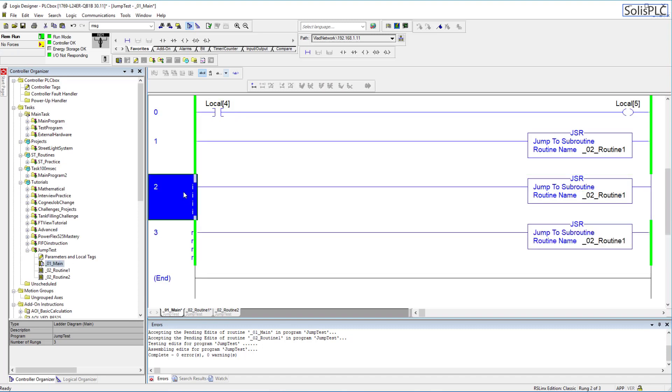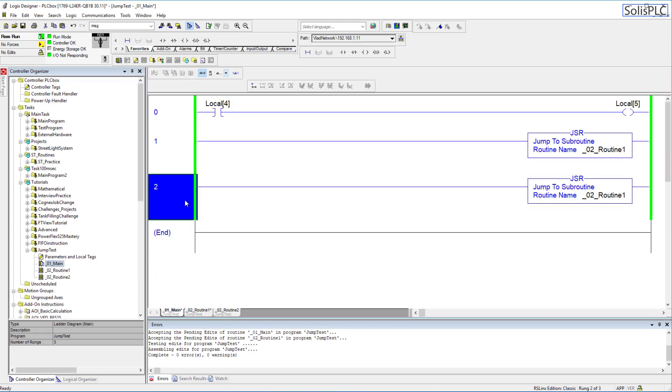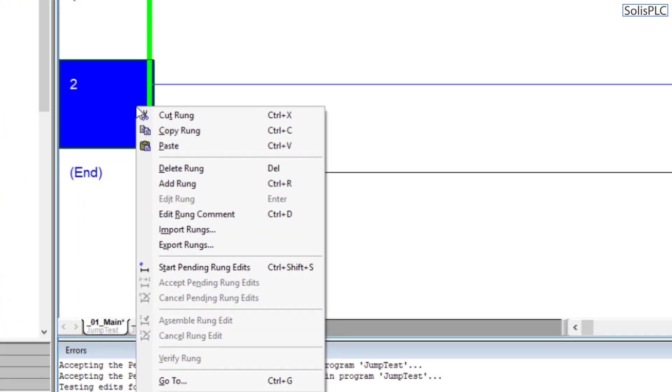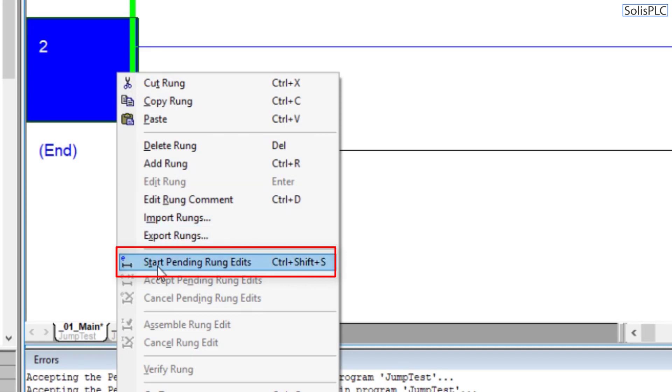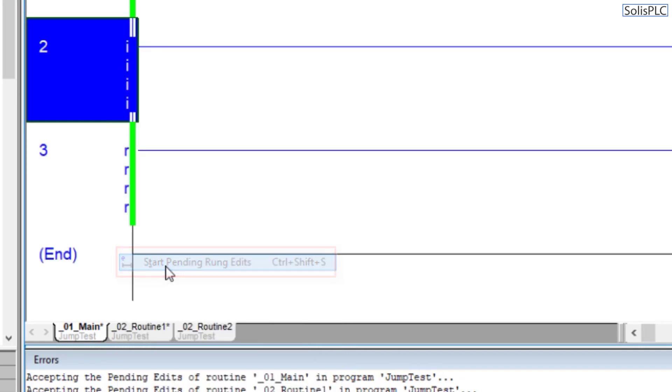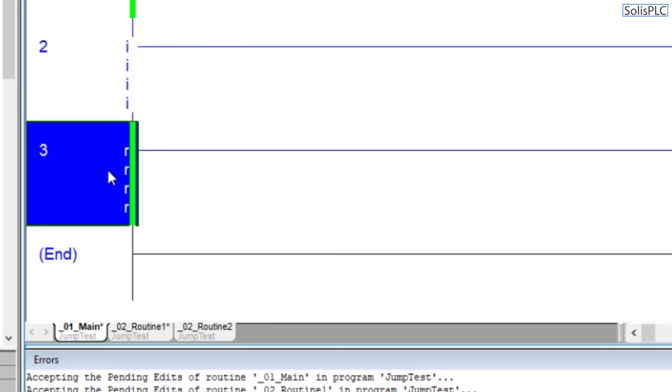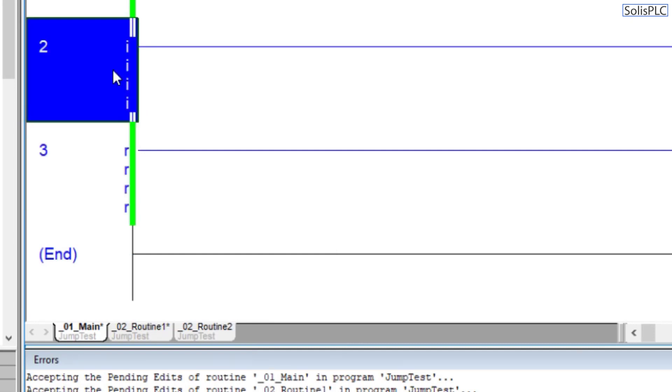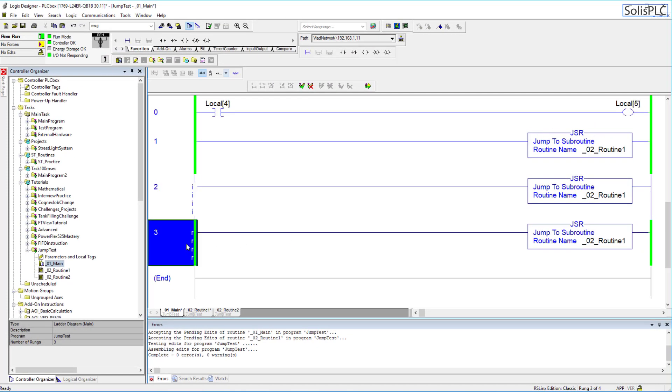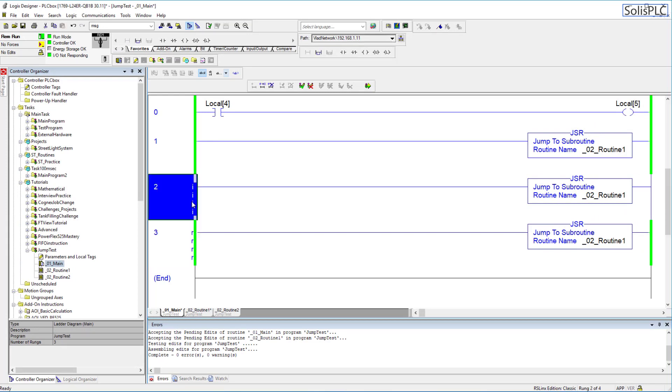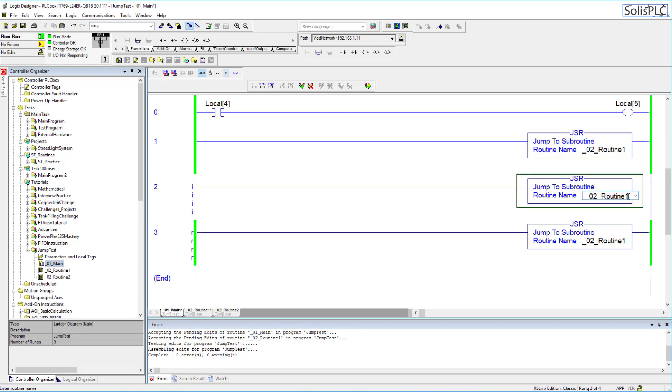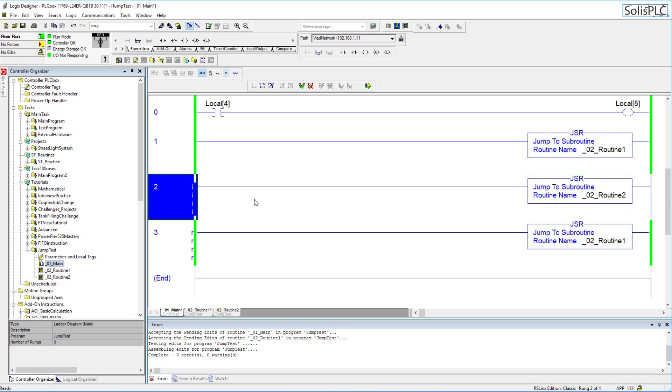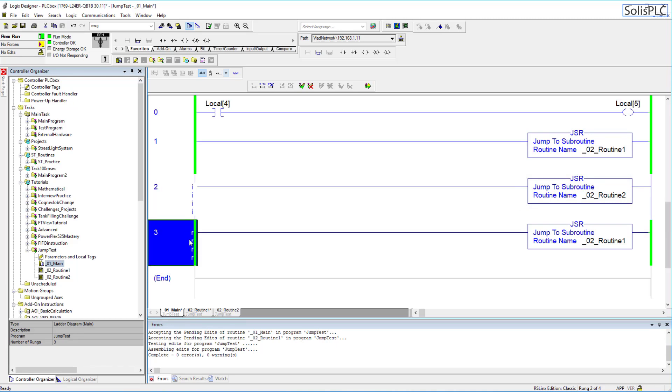Now going back to the main let's switch this back to routine 2. So just to demonstrate this for some of you who are not very familiar with the logic editing online. So once again I am online with my PLC if I double click the rung or if I right click and then I edit the rung so start pending rung edits I can select that you'll notice that there's going to be this in progress. I personally don't know what the letters mean but I can tell you that this is the rung which you're editing this is the logic that is currently being executed by the PLC. So until you commit your changes the previous version of the rung is being executed. So you can make any changes at this point. I'm going to change this to a 2 like so and notice that like I said this rung is still being executed since you have the green bar this one is not.